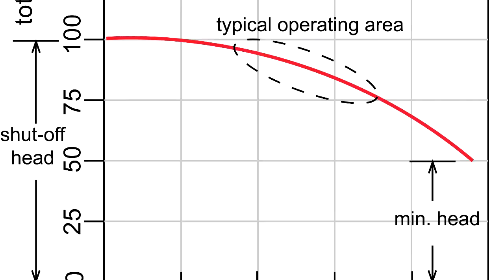Same thing applies if we go towards shut-off head which is at zero flow. If we shut the flow off at the discharge of the pump then the fluid would recirculate inside the pump and it'll overheat or damage the pump. So there's a comfortable area in between where we have the highest efficiency and that's where we want to operate.